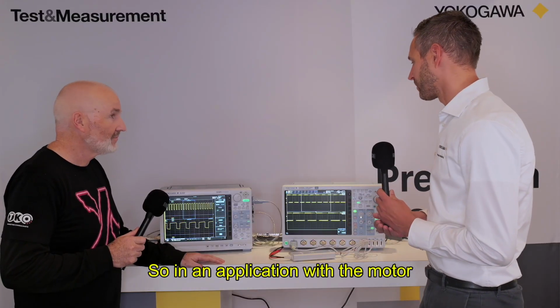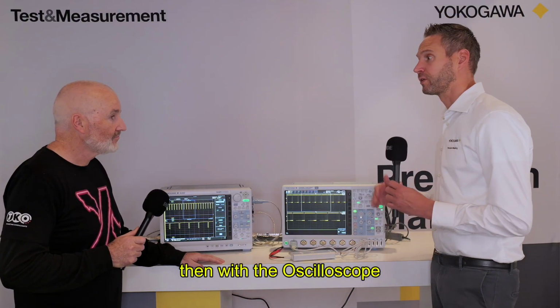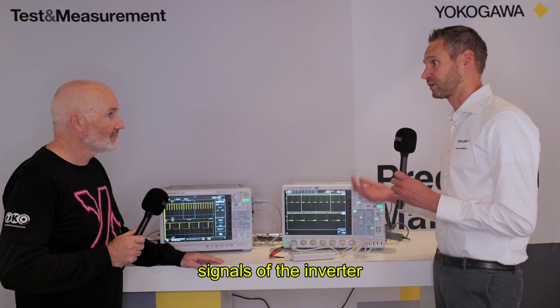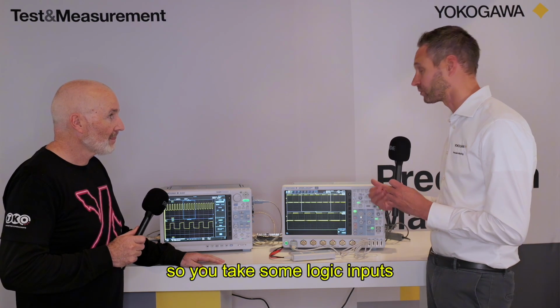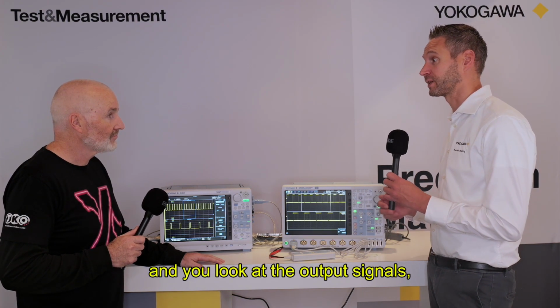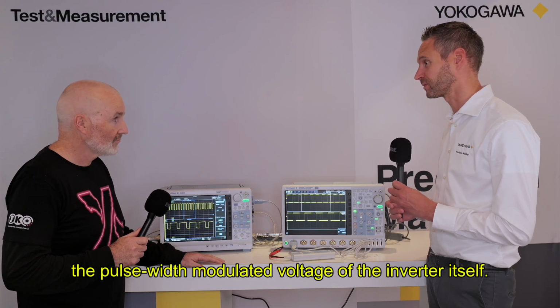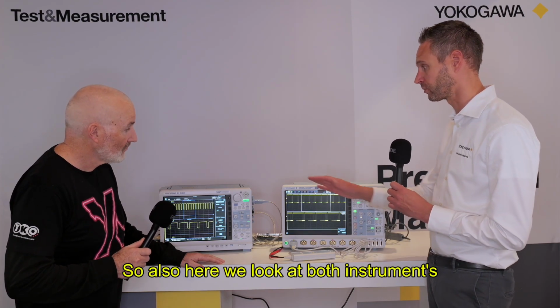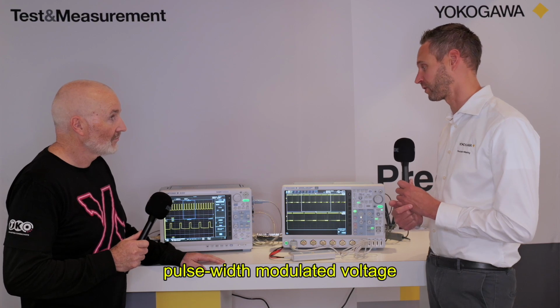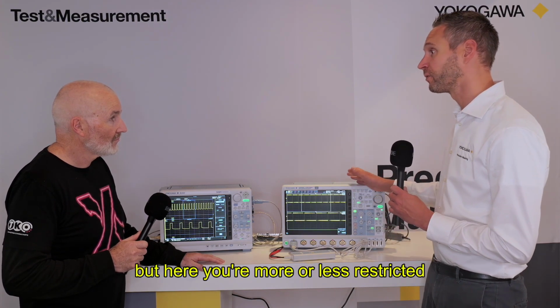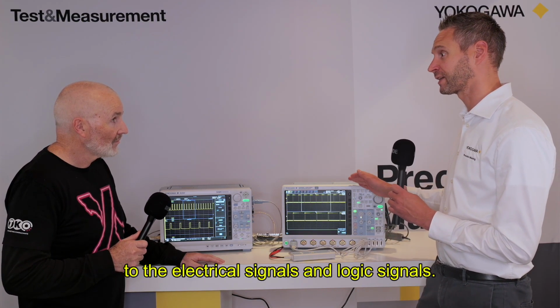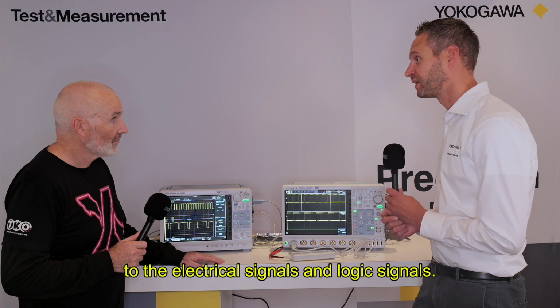So in an application with the motor, with the oscilloscope you're looking at the control signals of the inverter. You take some logic inputs and you look at the output signals, the pulse width modulated voltage of the inverter itself. So also here we look on both instruments at the pulse width modulated voltage. But here you're more or less restricted to the electrical signal and logic signals.